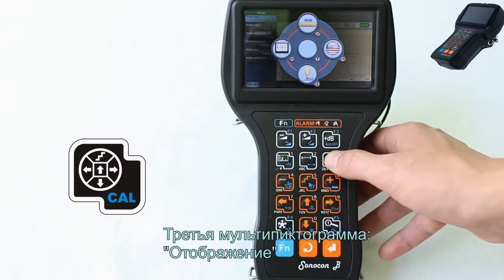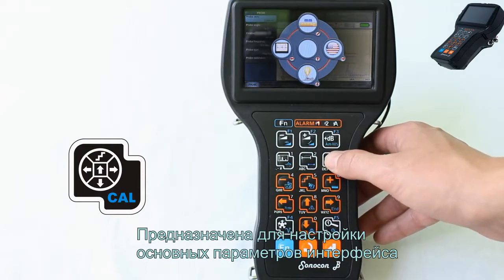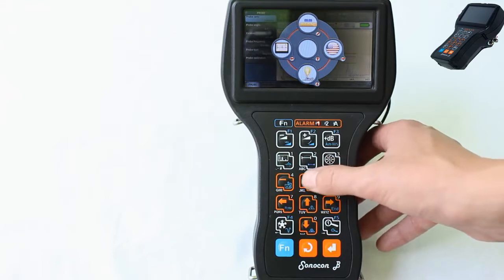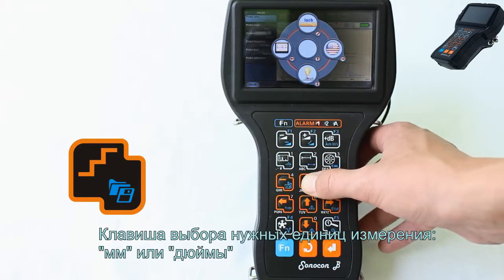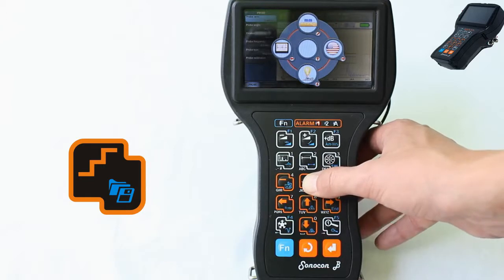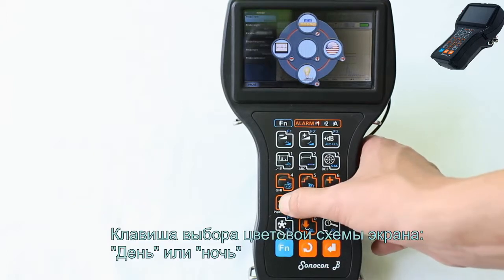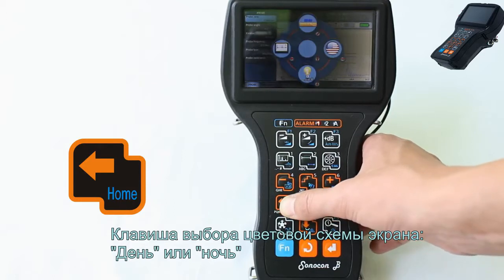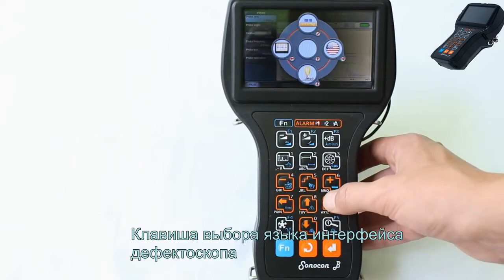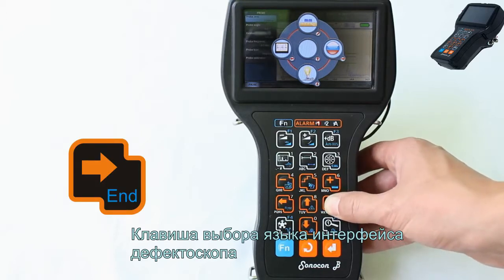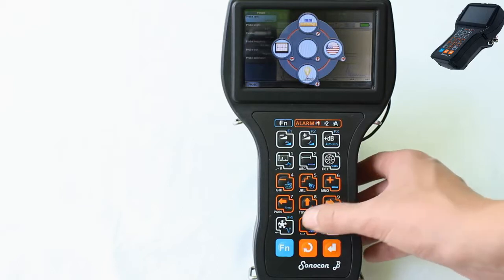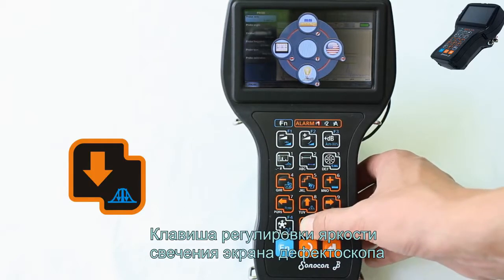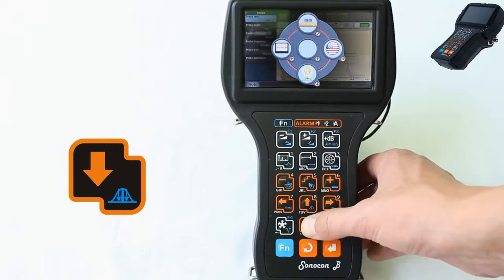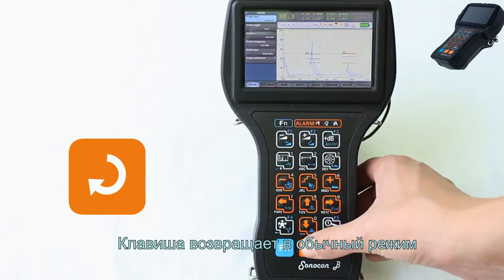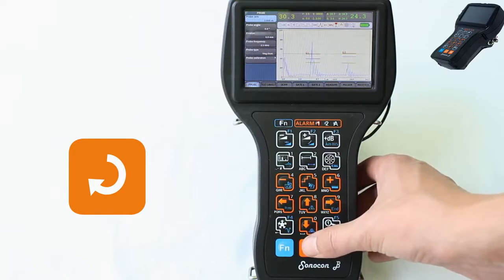The third multi-icon, Display, is intended to set up the basic parameters for the interface. Button for choosing the appropriate measurement unit, mm or inch. Button for choosing the color scheme of the display screen, light or dark. Button for choosing the language of the flaw detector interface. Button for adjusting the brightness of the flaw detector display screen. This button returns the instrument to the normal mode.